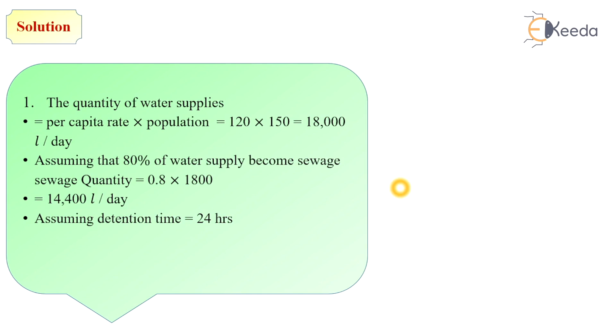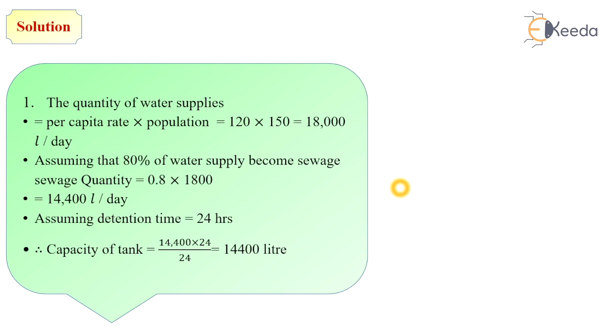We assume the detention time as 24 hours. From sewage flow and detention time, we calculate the capacity of tank. Capacity of tank equals total sewage flow per day: 14,400 into 24 divided by its detention time of 24, which equals 14,400 liters. So capacity of the septic tank is 14,400 liters.